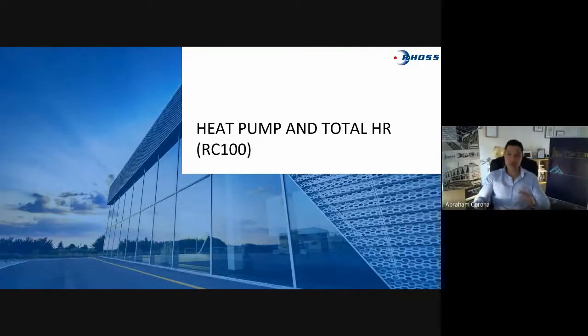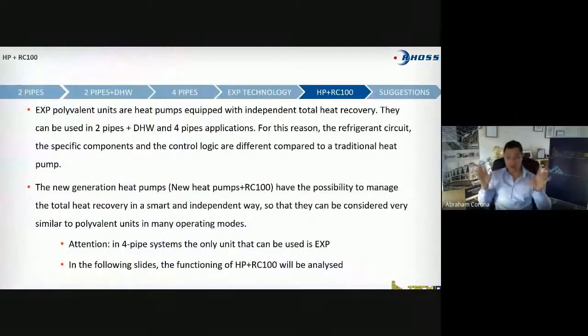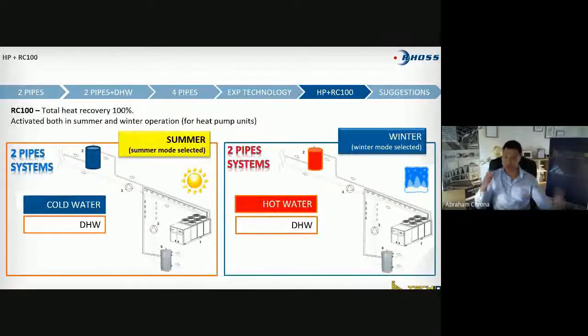With a total heat recovery, it will give you some savings in money, if you really know what you're doing, of course, and you know the consequences. That's the reason we are comparing that. So if the system is a 4-pipe system, that you now understand, you need to go polyvalent. You need to go EXP 100%. But let's say you have a requirement where you need a 2-pipe with heat recovery. The good thing is, for example with us, we now have what we call a new generation of heat pump, smart heat pumps. In other words, we are able to supply even hot water on the recovery without the demand of the primary sometimes. But that will have some risk. This is a scenario where a smart heat pump in summer months can work as a chiller that will give you cold water, and in winter months will give you hot water.